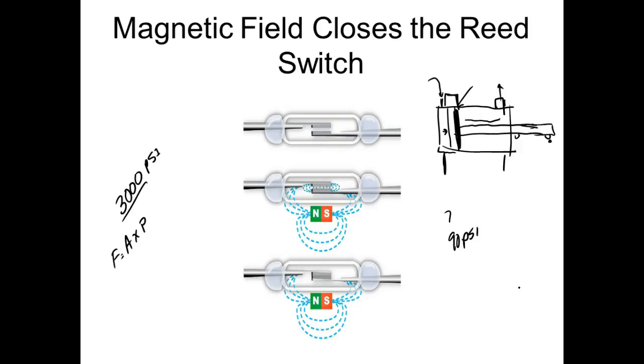But instead of just using a metal cam out there that the limit switch hits, now I would replace it with a what? A magnet. So you see. It lasts longer too. Well, but yeah, it lasts longer because it's not an electro, well, that's not true. A reed switch is electromechanical. But the reed itself, the switch, is in a vacuum, which means it's very low stress.